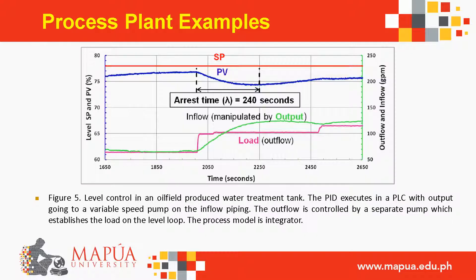Level control in an oil field produced water treatment tank: the PID executes in a PLC with output going to a variable speed pump on the inflow piping. The outflow is controlled by a separate pump which establishes the load on the level loop. The process model is integrator.